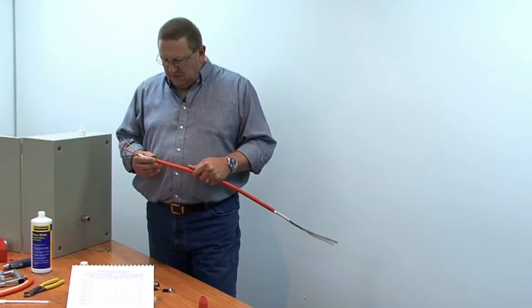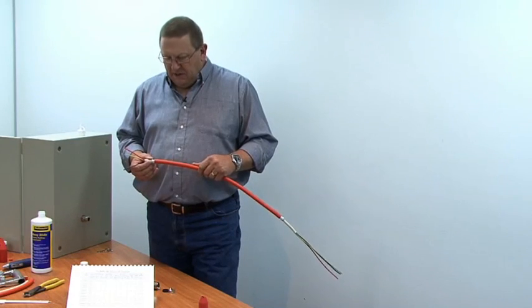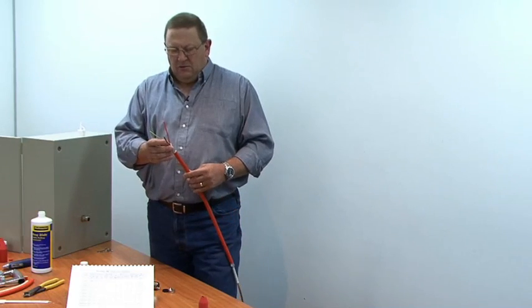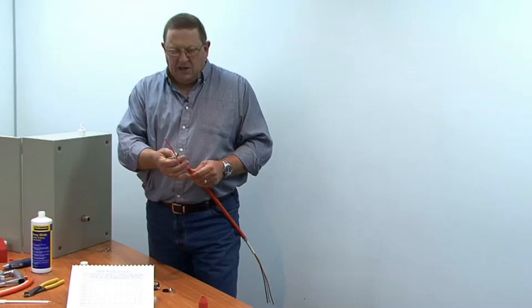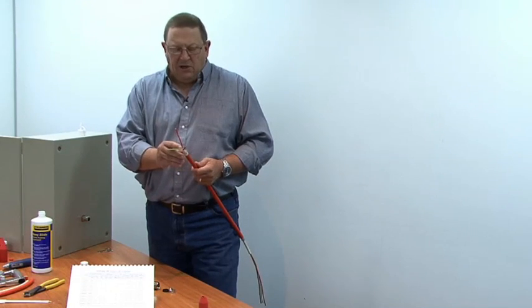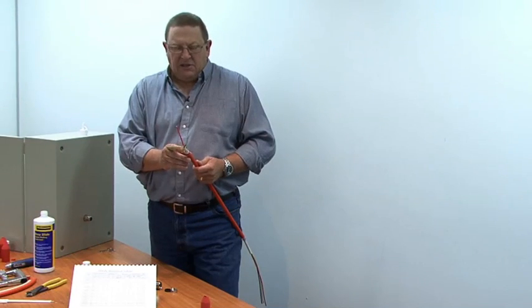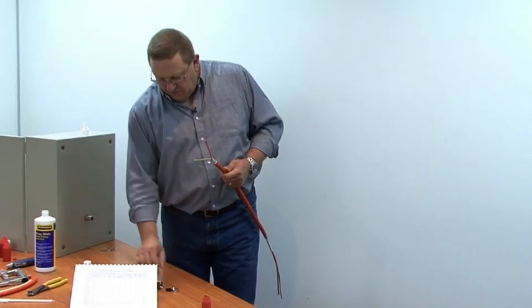The fitment is very similar in that we still need grounding cones. The one fundamental difference is that we use an epoxy compound between the cores. On larger builds, the voiding between conductors, even with packing, sees the dimension being distorted or not round or with holes, so we can't use a circular seal because it won't completely do the job.